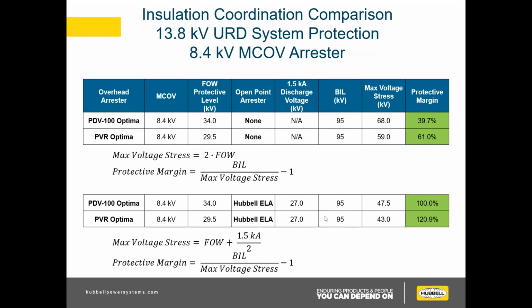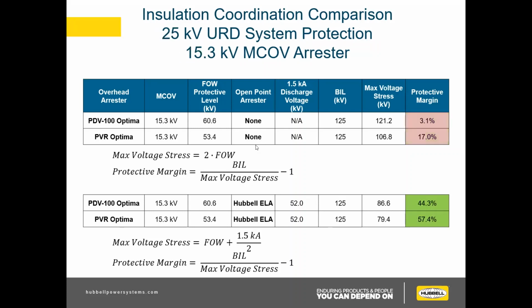We'll go over the next few examples really quick, just to see where it starts to really jump. Your protective margins are hurt at higher voltages. This is at 8.4 kV. The next one is at 15.3. This is without your elbow arrestor. You're at 3% and 17%, even with the PVR Optima. So you're not really in a good spot here.